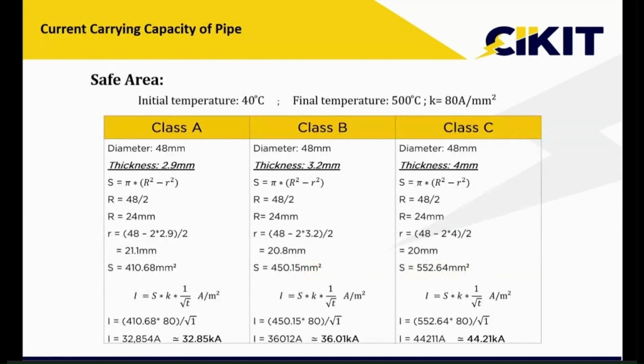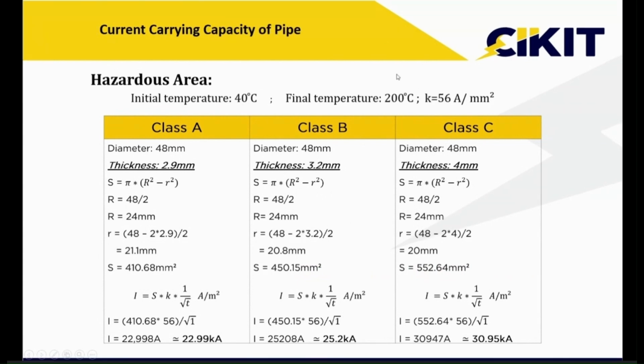Whenever we are working with cross-section area, the most important thing is whether we are working for a safer area or a hazardous area. If you take a normal area, which is a safer area, the final temperature will be considered as 500 degrees centigrade. Whereas if you are going for a hazardous area, the final temperature will be restricted to 200 degrees centigrade. Because of this restriction in the final temperature, the current carrying capacity of the conductor will be lesser, because whenever current flows through any conductor, heat will be produced. The heat produced will be proportional to I squared into R.